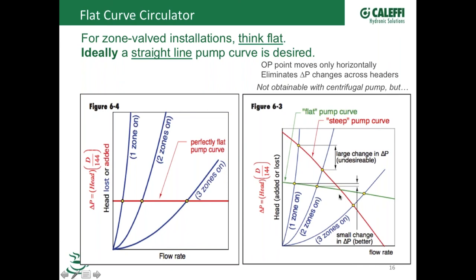So as the zone valves shut off, you're not changing that differential pressure by a lot as you would on a high head pump, if that makes sense. So when all the zone valves are open and you're out here at the operating point, you're getting 12 gallons a minute divided amongst all the zones that are open. You're just right at your design condition, but as the valves start shutting off, you're going to start running up that pump curve.